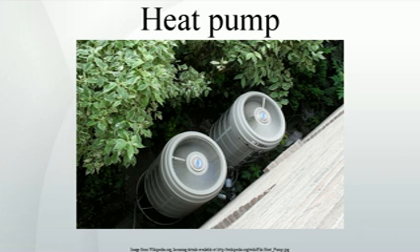At least two manufacturers are selling heat pumps that maintain better heating output at lower outside temperatures than conventional air source heat pumps. These low-temperature optimized models make air source heat pumps more practical for cold climates because they do not freeze and shut down as readily. Some models, however, defrost their outdoor unit using electrical resistance heating at regular intervals, which increases electricity consumption dramatically during the coldest periods.